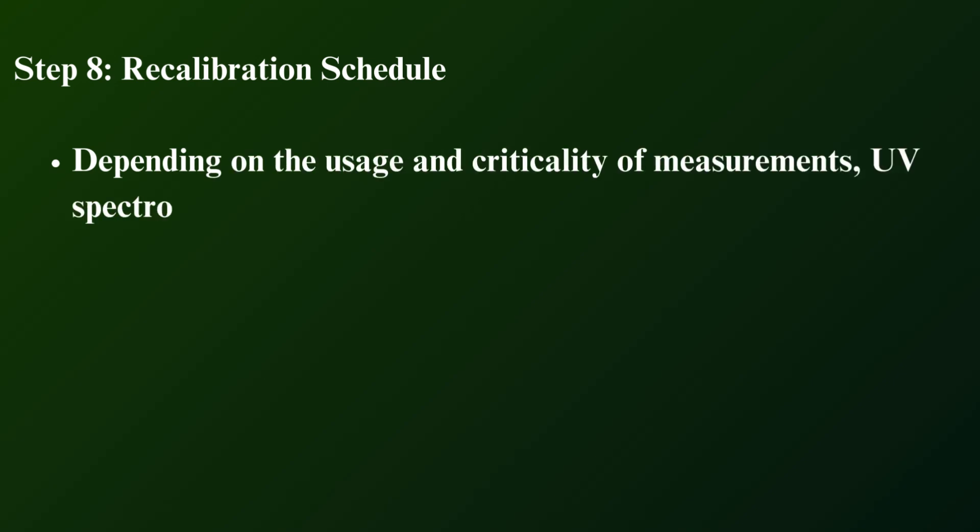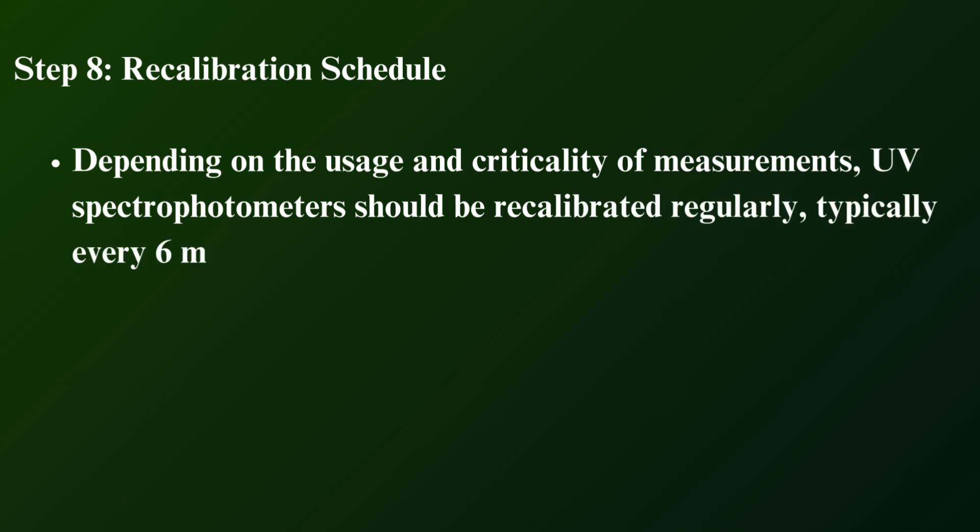Step 8: Recalibration schedule. Depending on the usage and criticality of measurements, UV spectrophotometers should be recalibrated regularly, typically every 6 months or before any critical batch analysis.